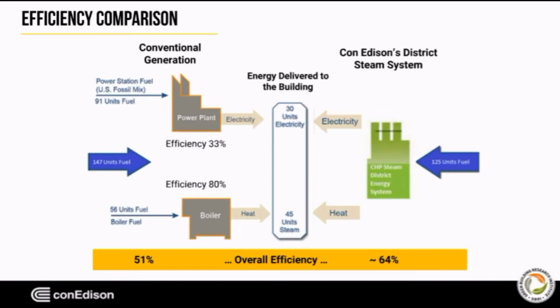To more clearly understand the picture of efficiency, we can take a look at an example. According to estimates from the EPA, the conventional generation heat and power system uses 147 units of energy, 91 for electricity and 56 for heat to produce 30 units of electricity and 45 units of steam. On the other hand, we have Con Edison's district steam system using CHP, cogeneration, which in this scenario would use 125 units of energy input to produce the same 75 units of useful energy, heat and electricity, from one single source. This results in a total system efficiency of 64%, compared to 51% for the conventional energy.